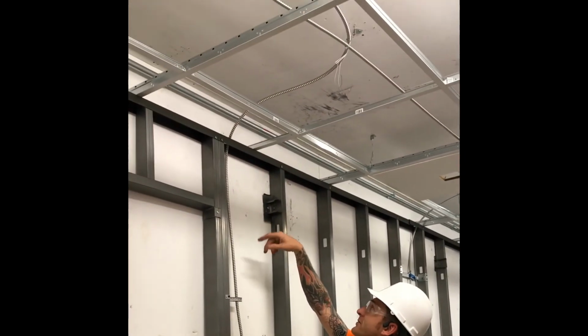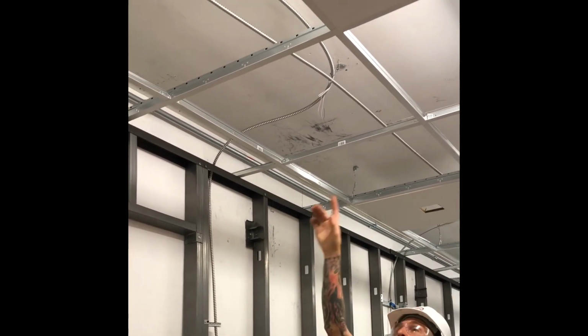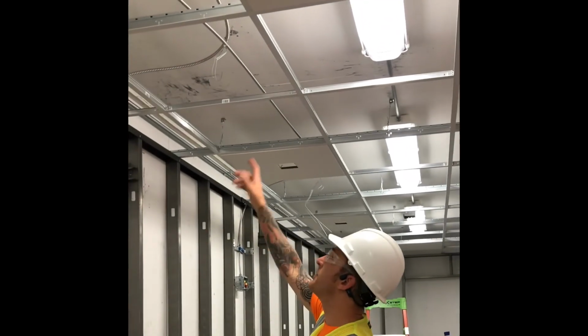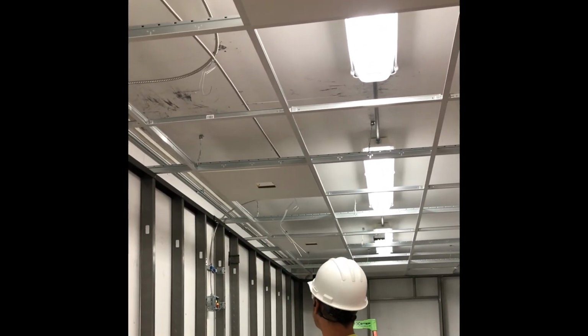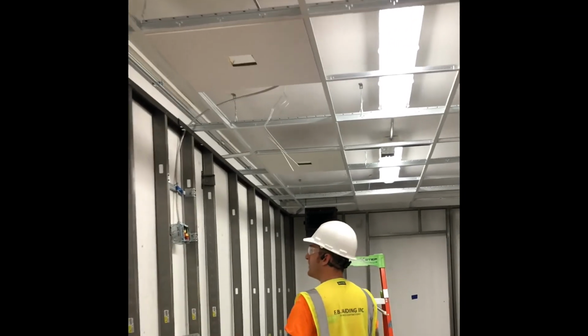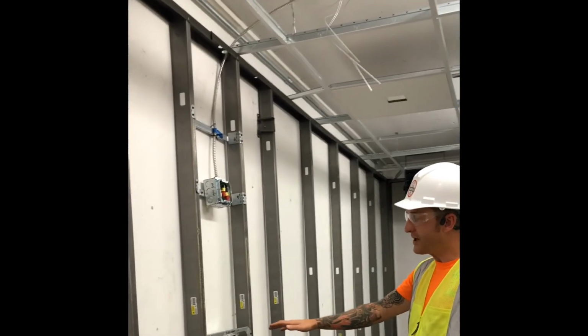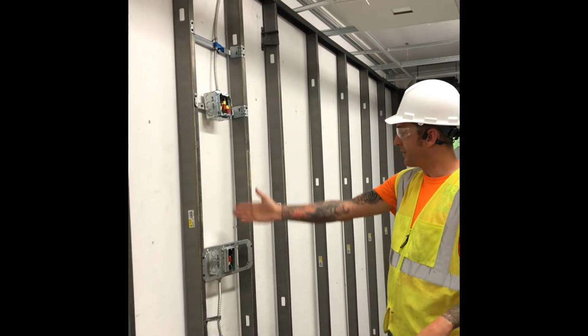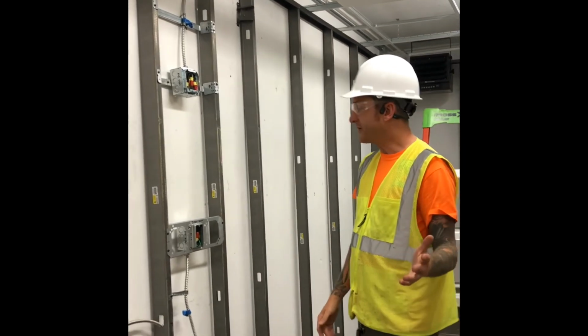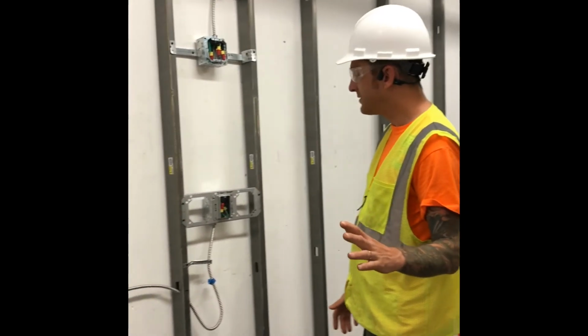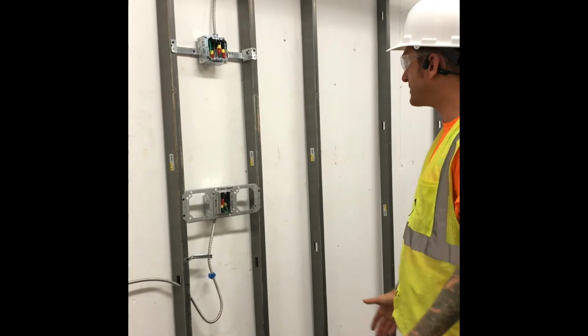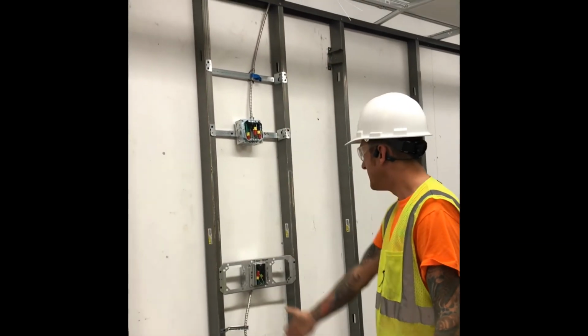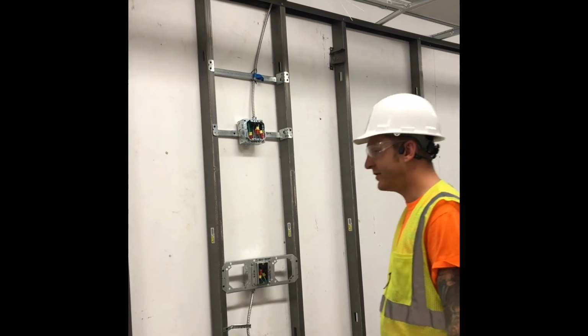What else we're looking for is the ceiling, like I was talking about earlier, making sure the cable's going through the stud, supports going up there. The ceiling itself you're not too worried about, since that's a totally different ceiling inspection, but you want to make sure it's going into the right location and labeled correctly. Boxes should be straight at the right dimension, especially ones in line with each other, which we talked about earlier. A vertical laser, I'll get into that in another exercise, basically makes sure you're completely straight vertically.